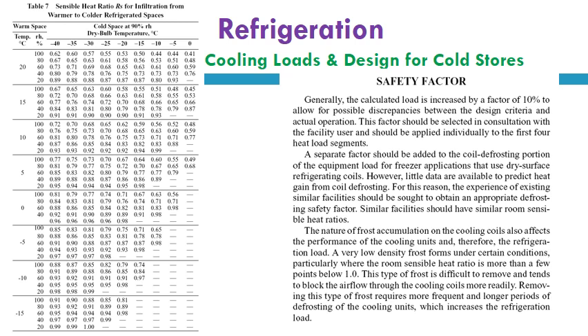Here we can find the continuation of the previous slide, table number 7, which was discussed in the previous slide, and now we will go to the safety factor, and the basis of taking a safety factor during the design stage. Generally, the calculated load is increased by a factor of 10% to allow for possible discrepancies between the design criteria and actual operation. This factor should be selected in consultation with the facility user and should be applied individually to the first four heat load components or segments which have been discussed: transmission load and internal load, infiltration load, and product load.